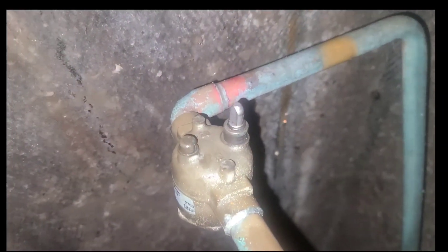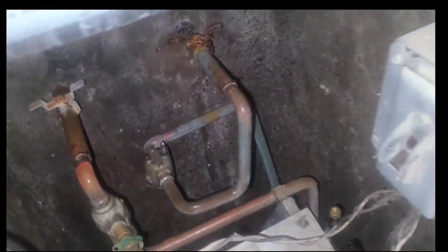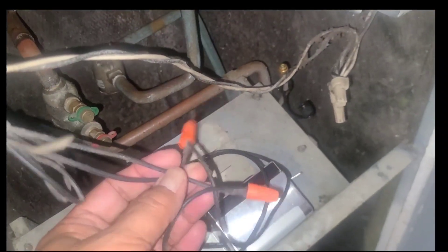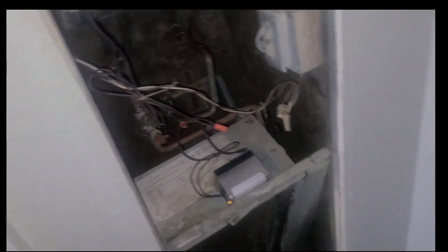Here it is right here — that's our valve there, and our actuator. Here's the old one. All of this is two wires. The two wires are not polarity sensitive, so it does not matter which wire goes on which side. Let's go ahead and install it.